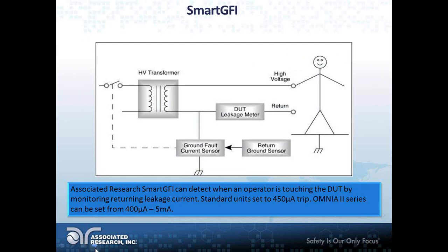So let's look at our SmartGFI. This is pretty much on every one of our units. Some of our older instruments didn't have this. This was built in a little bit later, but all of our current instrumentation that you can find on our website right now all have a SmartGFI circuit built into it.